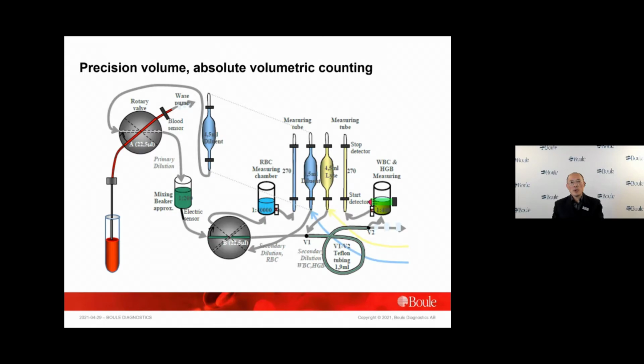Here, the total number of cells is measured by the size of the voltage deflection caused by the particle passing through the aperture, and also the shape of the curve. Algorithms can determine the cell volume, and by this, the instrument can make a plot called a histogram to show the distribution of different sizes of cells in the blood passing through the measuring aperture.